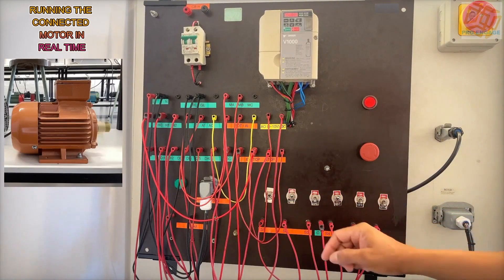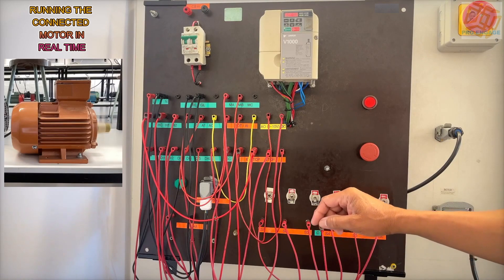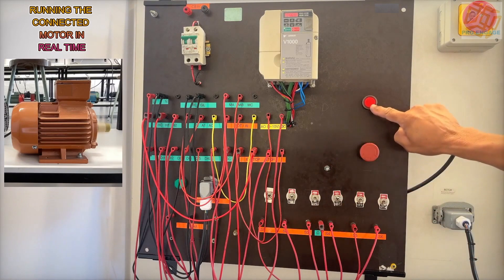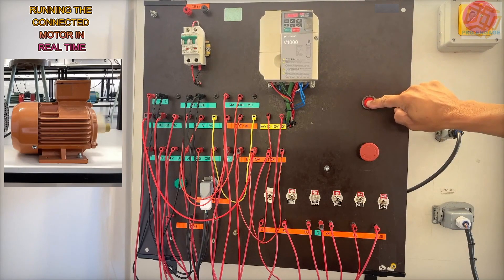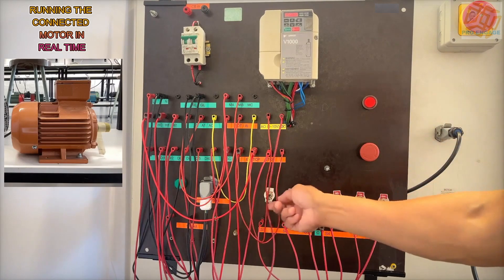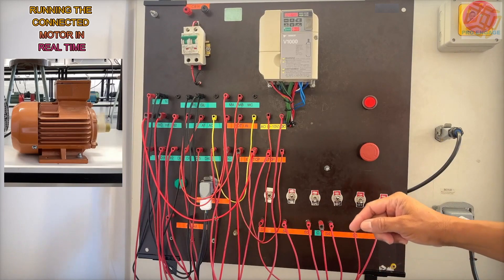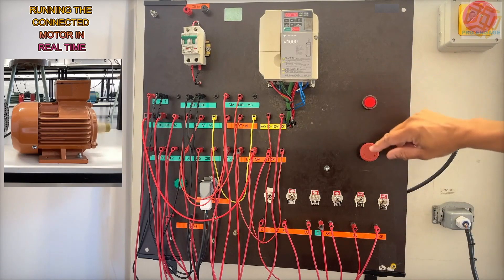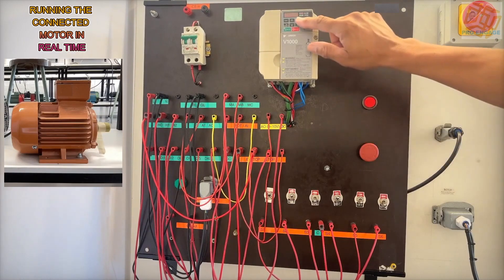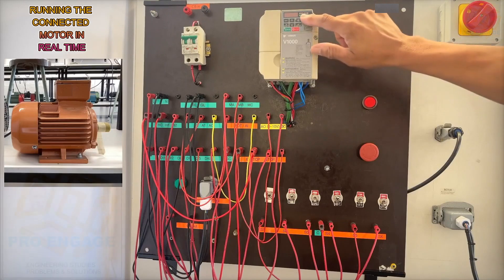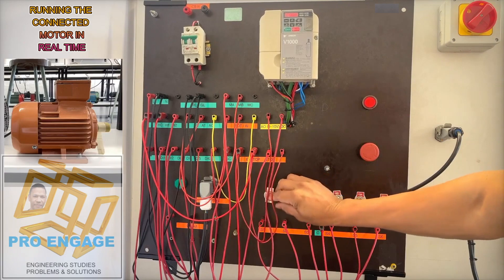Let's start up and do something else, maybe do the stop buttons. You can see it's running, it stops immediately, there's a message and then the signal goes away until we start it again. The e-stop is different. It will keep the message on the screen because the e-stop locks the system. There we can see it stays there until the e-stop is reset. We push the buttons down and then we can restart the motor again.